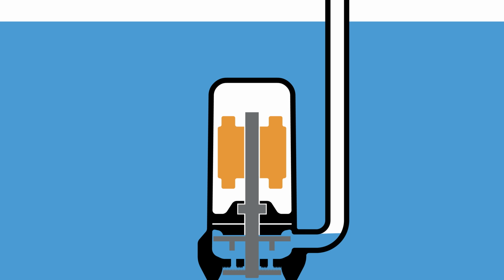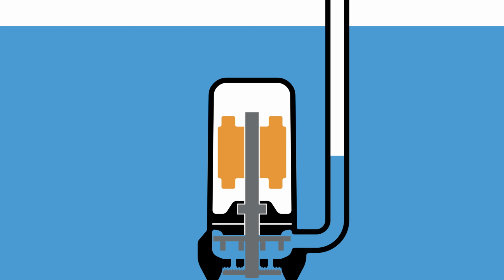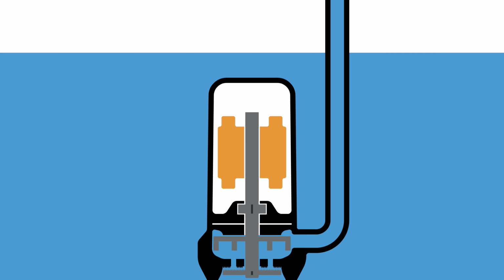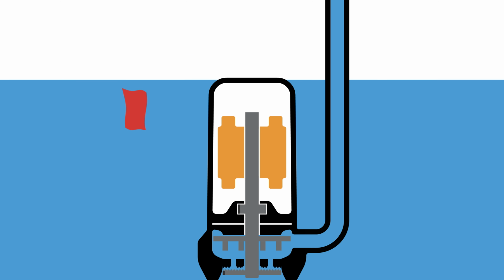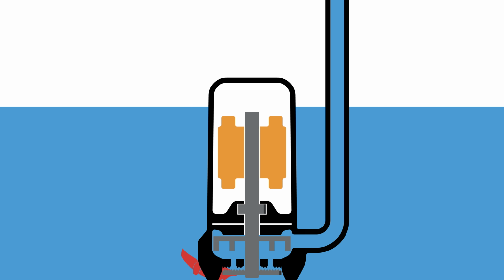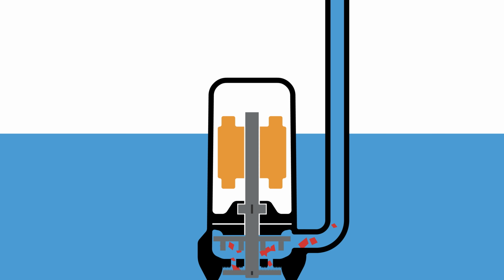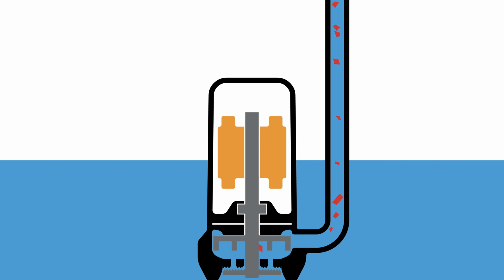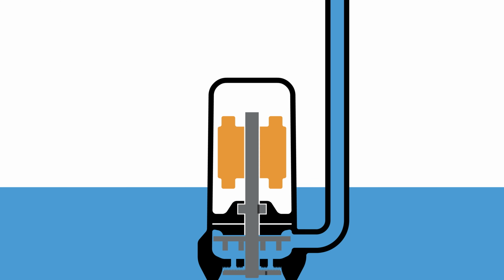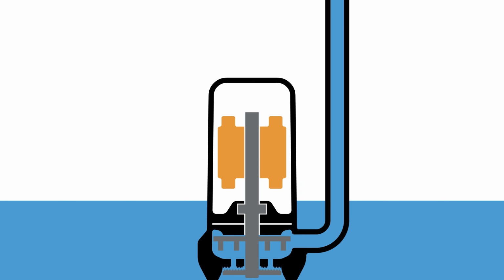This video will go over methods and procedures for starting up a 3-wire, single-phase grinder pump with a control panel. A 3-wire grinder pump requires the capacitor kit to be wired into the control panel. Warning: only qualified licensed personnel should perform actual tests and wiring on the control panel and grinder pump wiring. Shock hazards may lead to injury or death.